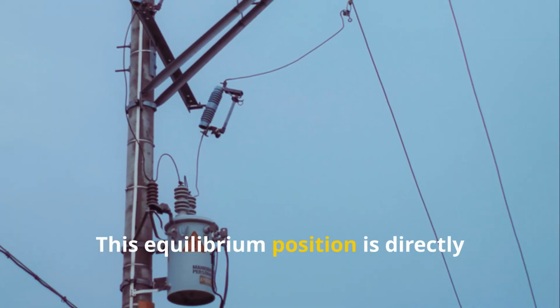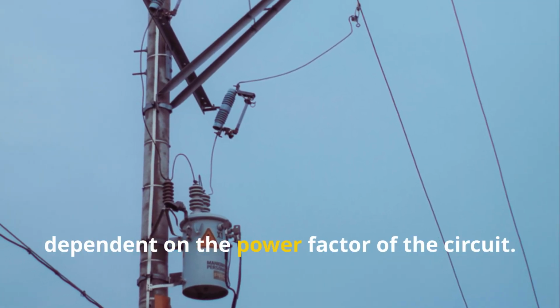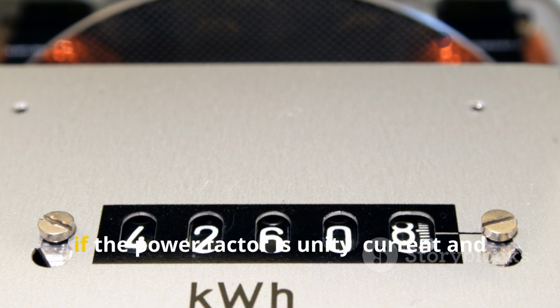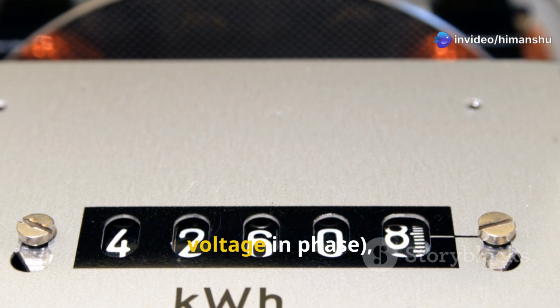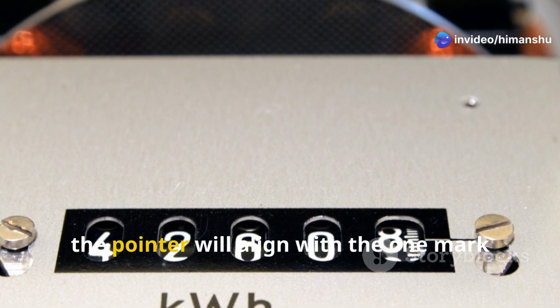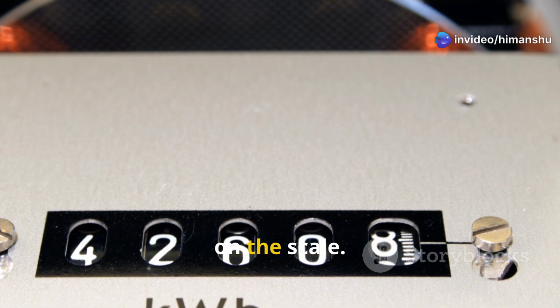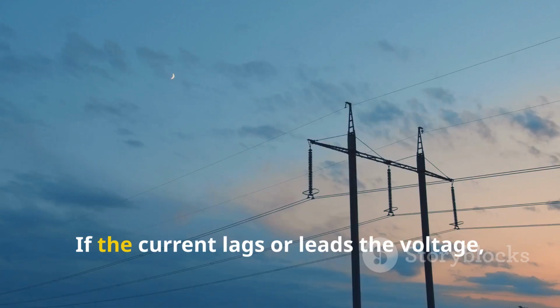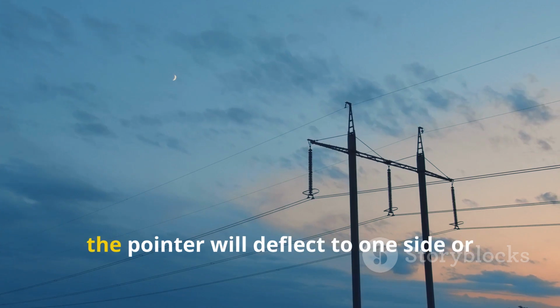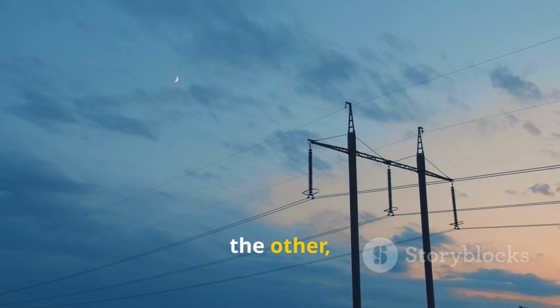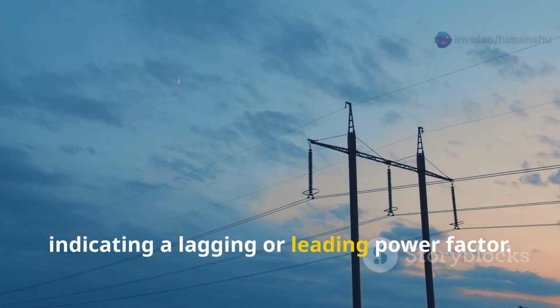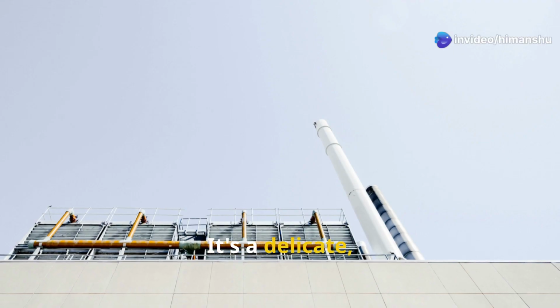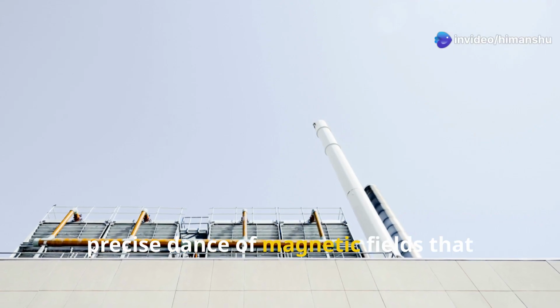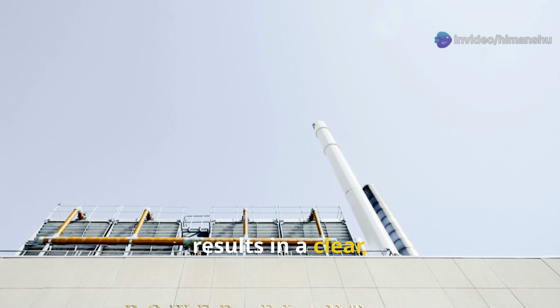This equilibrium position is directly dependent on the power factor of the circuit. For example, if the power factor is unity, current and voltage in phase, the pointer will align with the 1 mark on the scale. If the current lags or leads the voltage, the pointer will deflect to one side or the other, indicating a lagging or leading power factor. It's a delicate, precise dance of magnetic fields that results in a clear, readable measurement.